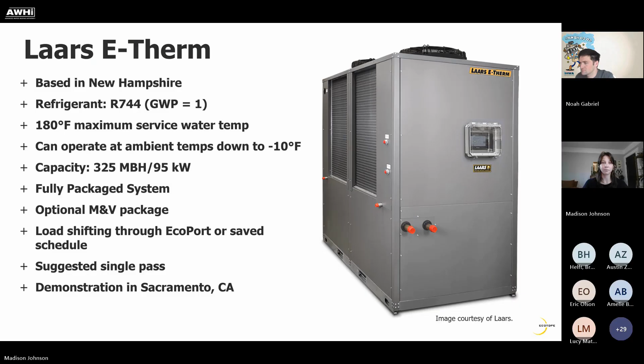We're looking at similar results for the Laars E-Therm. We have an annual, or projected, system COP in Sacramento of 2.7. EcoSizer engine estimates a thermal shift capacity of about 144 kilowatt hours, with an electrical shed capacity of 44 kilowatt hours in the summer and 63 kilowatt hours in the winter. We typically see higher COPs in summer and lower COPs in winter, and this is apparent in our electrical shed capacity — the system is more efficient in summer, so we have fewer kilowatt hours to shift outside that peak period.